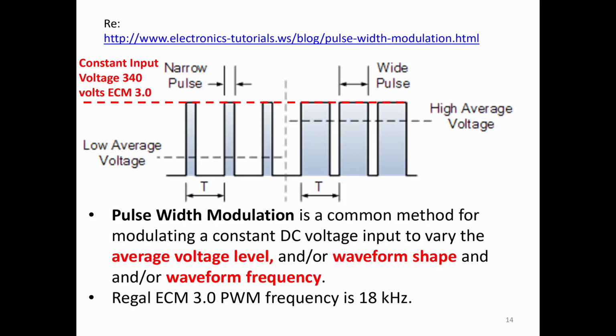This may be the most important slide in the deck with respect to understanding why ECMs are problematic. ECMs use pulse width modulation to modulate the DC voltage output, the triphasic DC voltage output, as a function of time. The frequency of the pulse train is fixed. Regal uses 18 kilohertz pulse width modulation. I'll give some other numbers for other devices later on. The reason the average voltage varies is because the duration of each pulse changes, and not because the amplitude of the pulse changes. So you can see I have a constant input voltage, and rather than the frequency changing, the average pulse duration changes.